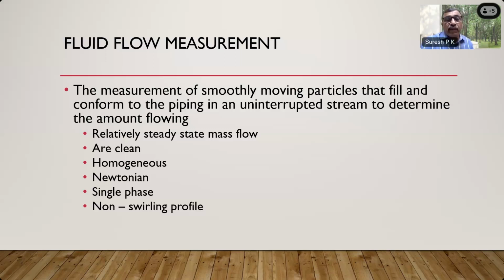One is that it is relatively steady state mass flow. That is, the fluid is steadily flowing without fluctuations. When you say the flow is 30 meter cube per hour, the flow remains 30 meter cube per hour, plus or minus something. But it's not varying from 30 to 0 and then 0 to 30. The flow meter will not be able to cope with such variations. So we are assuming that when a flow meter measures the fluid, the flow is steady mass flow.